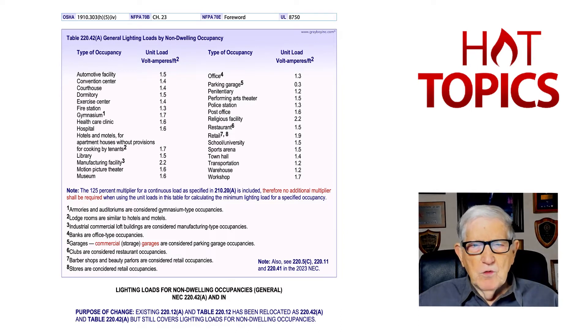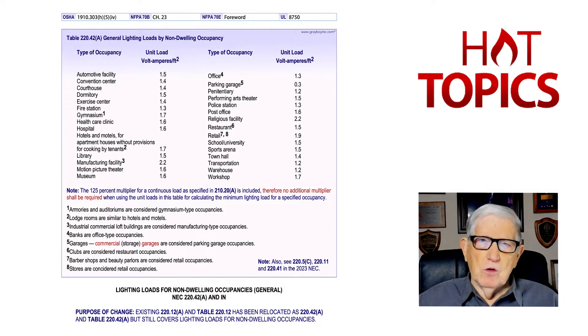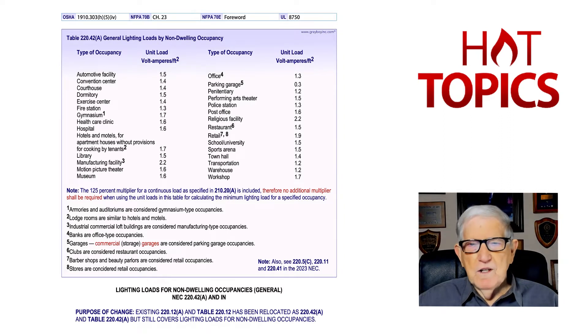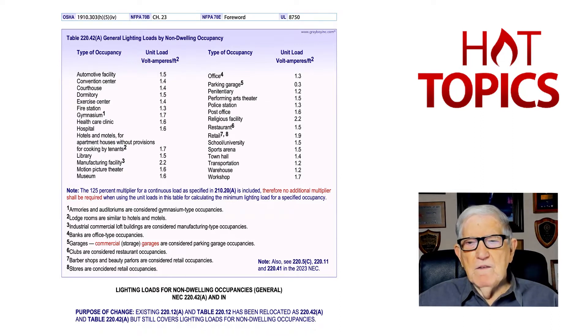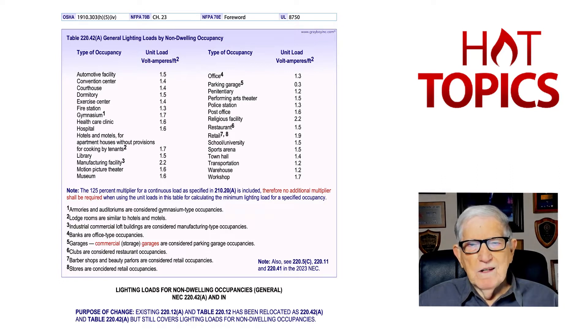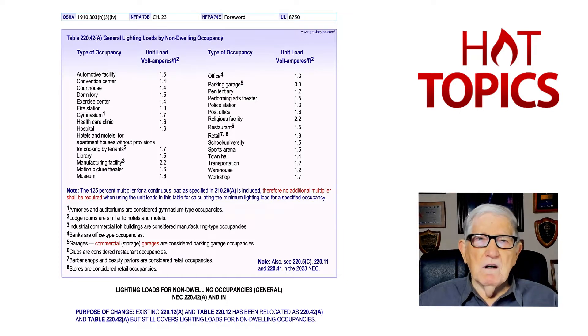The note says the 125% multiplier for a continuous load as specified in 210.20a is included. Therefore, no additional multiplier shall be required when using the unit loads in this table for calculating the minimum lighting load for a specific occupancy.